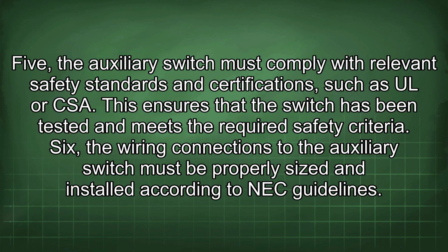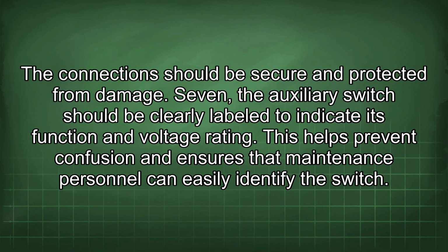5. The auxiliary switch must comply with relevant safety standards and certifications such as UL or CSA. This ensures that the switch has been tested and meets the required safety criteria. 6. The wiring connections to the auxiliary switch must be properly sized and installed according to NEC guidelines. The connection should be secure and protected from damage. 7. The auxiliary switch should be clearly labeled to indicate its function and voltage rating. This helps prevent confusion and ensures that maintenance personnel can easily identify the switch.